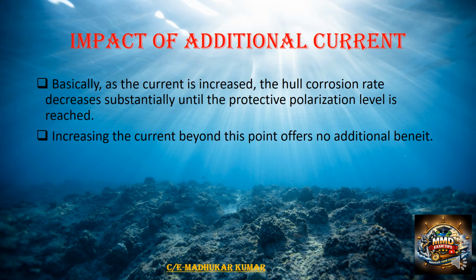Basically, when the current is increased, the hull corrosion rate decreases. We have seen that. But if you supply extra current, more current than required, it is not going to give any additional benefit. Basically, we are losing the amount of the excessive current. And if it is applied for a larger time, it is going to damage the hull protective coatings. So this is of no use if we supply excessive current. But when the current requirement increases, the hull corrosion rate also decreases. That is also the main factor you have to keep in mind.